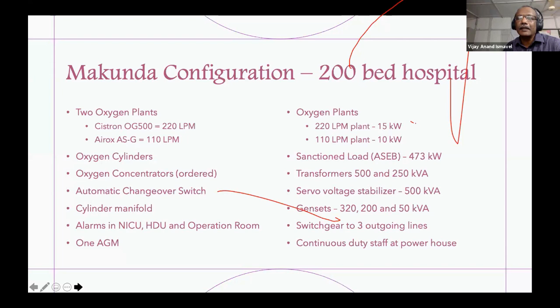How do you estimate consumption? Oxygen flow meters are very expensive, so a simple way is you disconnect all oxygen sources except the bulk cylinders, connect about 4 or 8 of them, connect the average load, and see how much time it takes to empty all 4 or all 8. Now we know the flow rate.